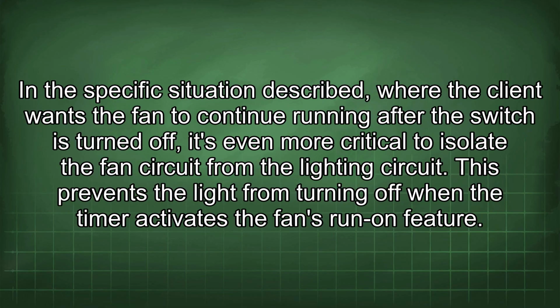In the specific situation described, where the client wants the fan to continue running after the switch is turned off, it's even more critical to isolate the fan circuit from the lighting circuit. This prevents the light from turning off when the timer activates the fan's run-on feature.